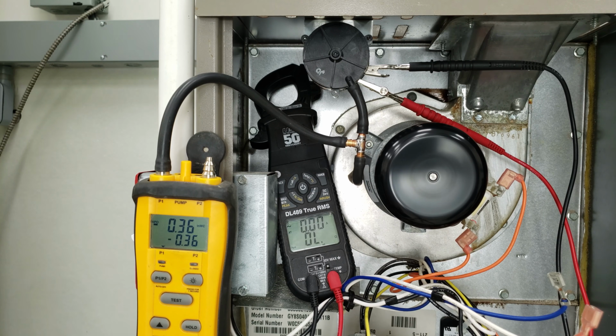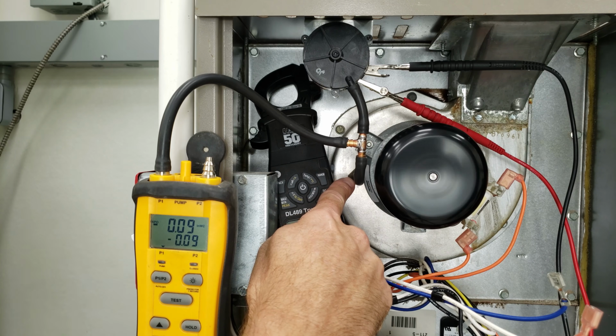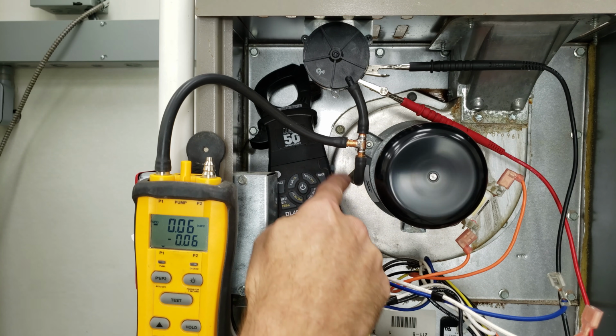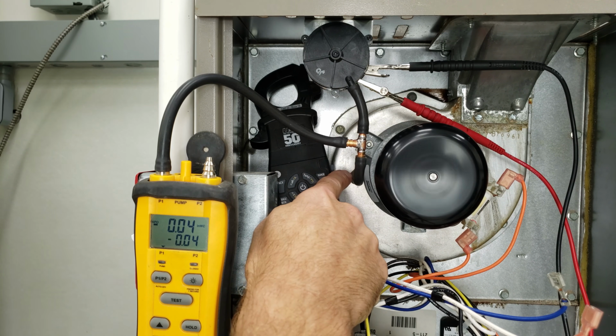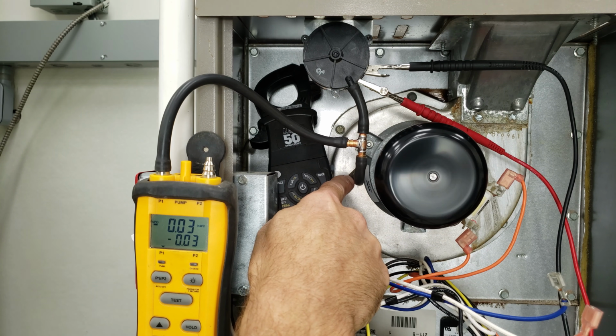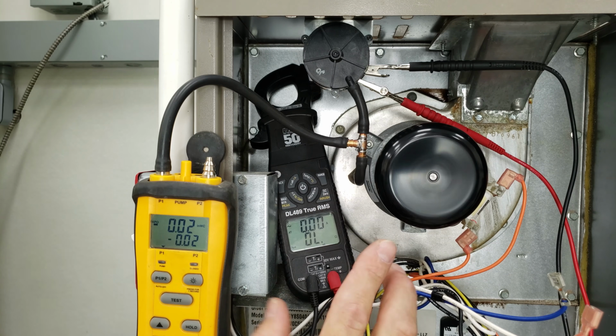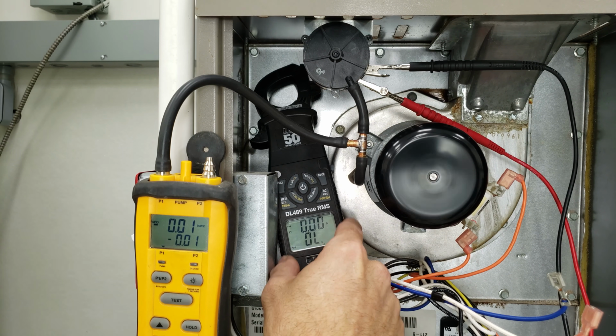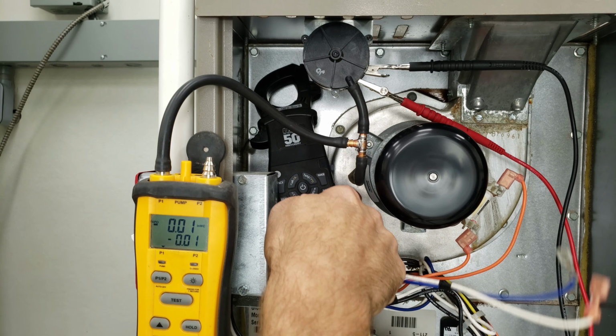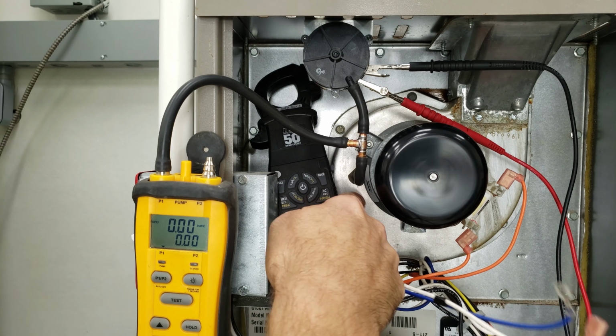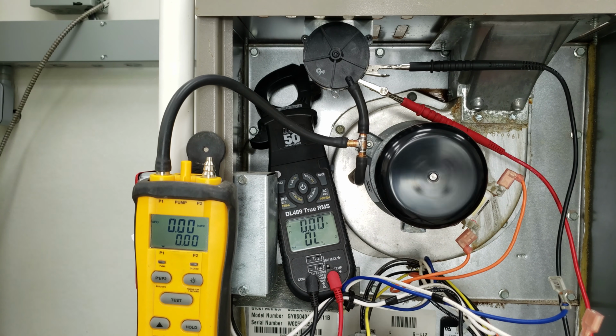So we're going to turn the power off. We're going to wait for that to stop, and then we're going to take a look at this port right here. A lot of times when you have a metal inducer motor housing, that port will clog solid right there. So that could be the issue. The other thing I just want to mention real quick is that we normally don't have our multimeter here because this inducer motor housing is going to get real hot. I just have it in there just for the photo.